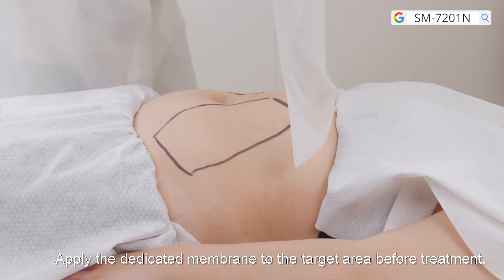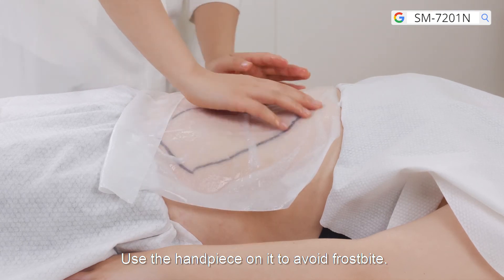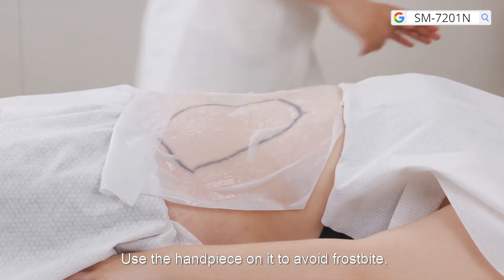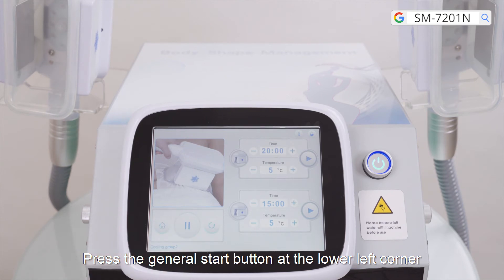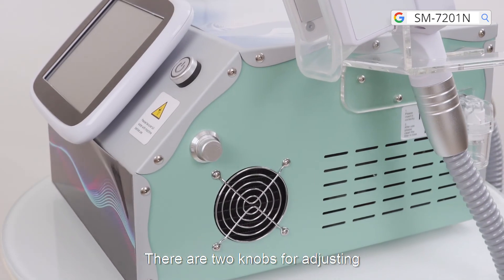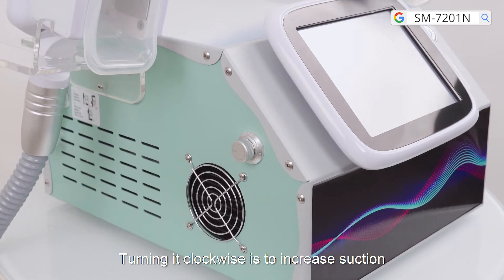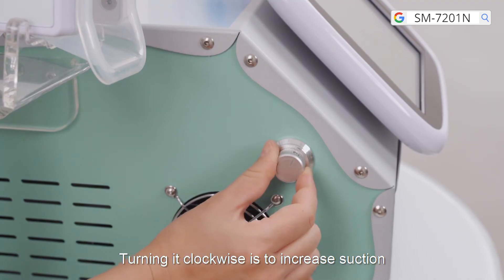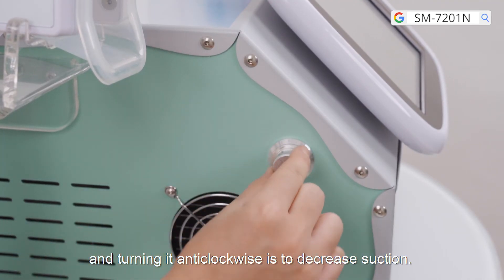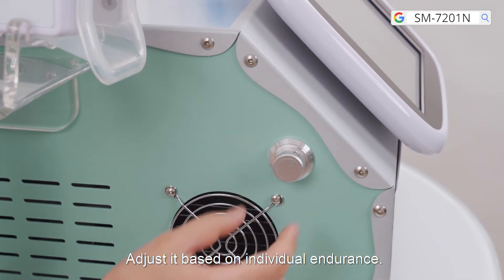Apply the dedicated membrane to the target area before treatment. Use the handpiece on it to avoid frostbite. Press the general start button at the lower left corner, then press the start button of the corresponding handpiece. There are two knobs for adjusting the suction levels of both handpieces — turn clockwise to increase suction and anti-clockwise to decrease. Adjust based on individual endurance.